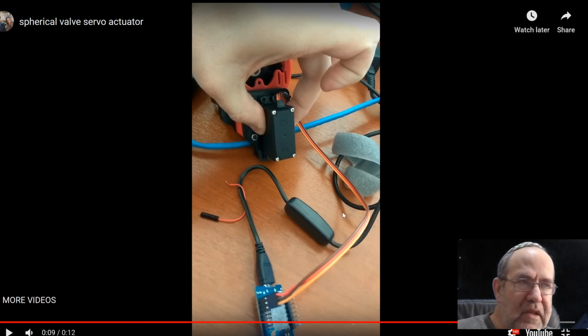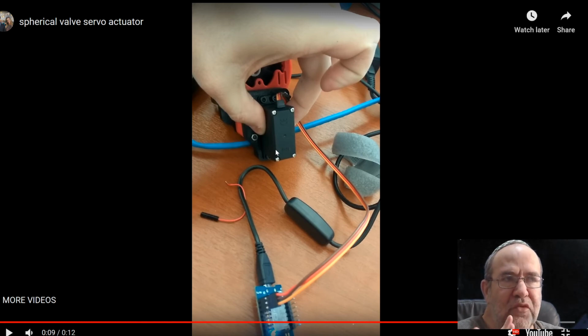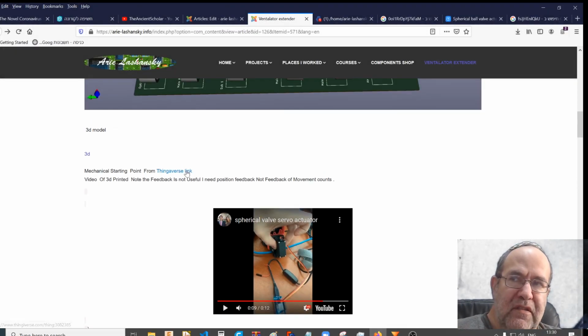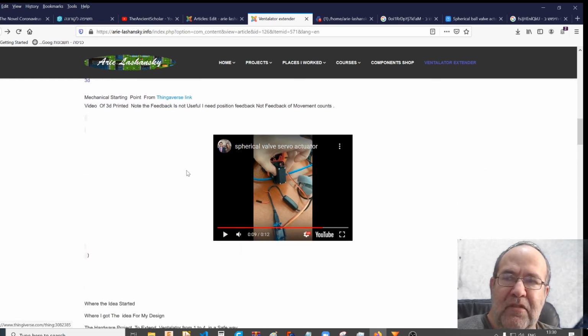This is from someone who made the product, but I can't use this type of mechanical feedback because I need to measure the exact position, not just the movement. If the system is switched off, or you miss pulses or counts, you don't want that uncertainty. I need an analog value that tells me the exact position of the valve, which means this 3D model would need to be adapted for what we're doing.